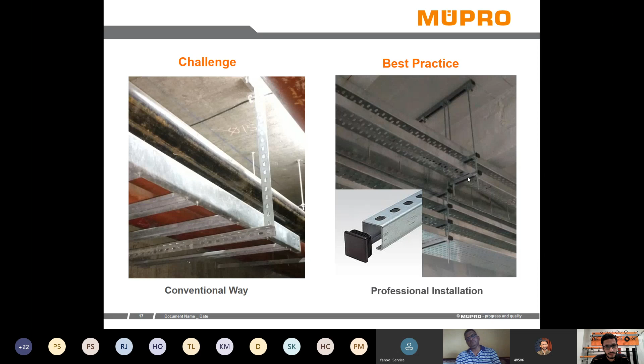Now this is one more way in which we can make our installations better. This is a single pipe which is installed with the help of an MS angle channel which is welded, and 8 anchors are used over here. And also once this support channel is welded, you cannot change the elevation of the support. Many a times there is a change of the elevation at the site after modification. In that case, this complete support has to be refabricated.